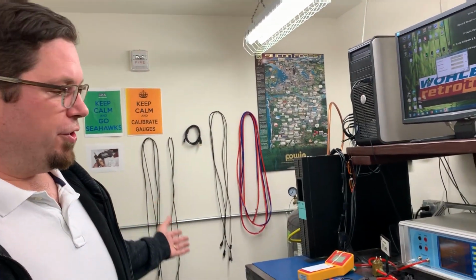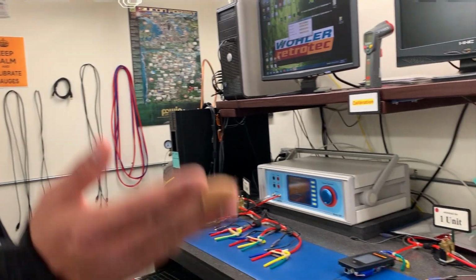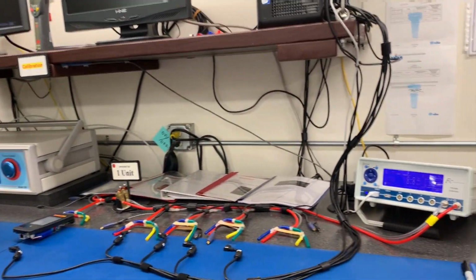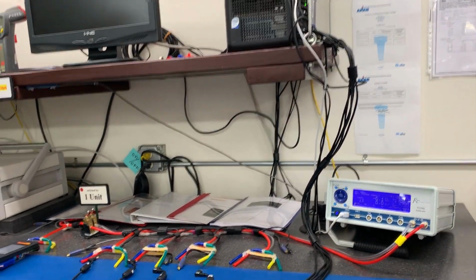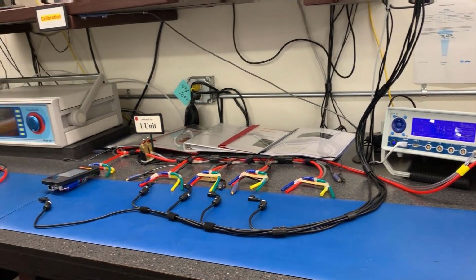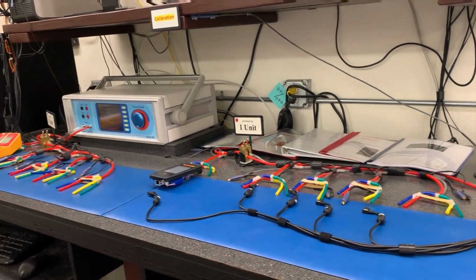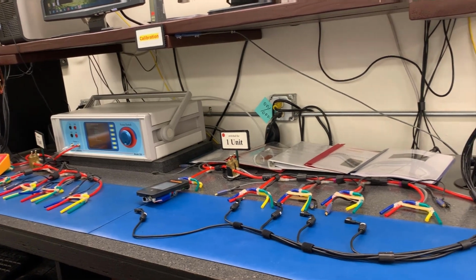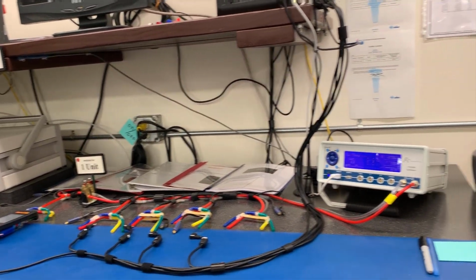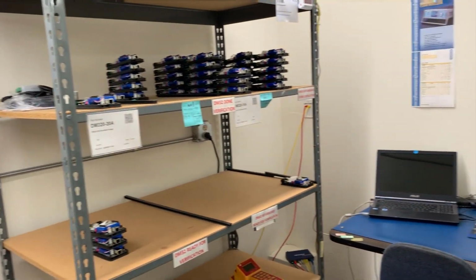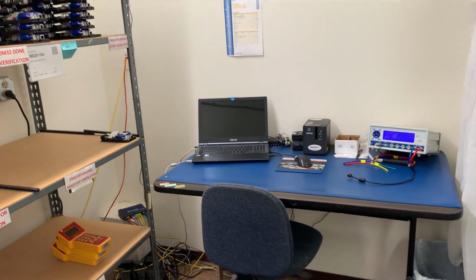And so as the gauges finish in production, they all line up here in queue on the shelf, get hooked up to the furnace calibration units here, and get run through our custom calibration program. And once all that is complete and the gauges have passed, then they finalize in here, the cases are finally snapped on, and they go back out onto the shop floor for storage in our cabinet and for shipping out to our customers.